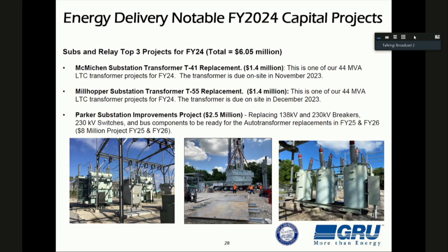Those breakers are filled with oil, and it's critical to replace them because there have been instances at other utilities, not on our system, where fires started inside substations because the circuit breakers couldn't interrupt a fault that occurred internally.